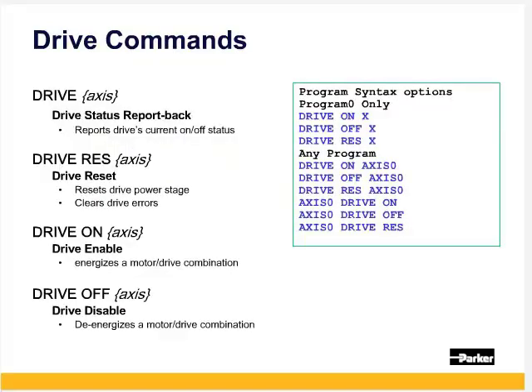The first set of commands are the drive commands. This allows to enable, disable, and reset of each axis. With our EPL demo, if both X and Y are attached to PROG 0 from our standard configuration, from the PROG 0 prompt, you can enable the drives from ACR View's terminal window by doing DRIVE ON X Y. The X and Y are aliases for AXIS 0 and AXIS 1 and are only recognized by PROG 0. At the SYS prompt or any other program prompt, you can enable with DRIVE ON AXIS 0 AXIS 1.